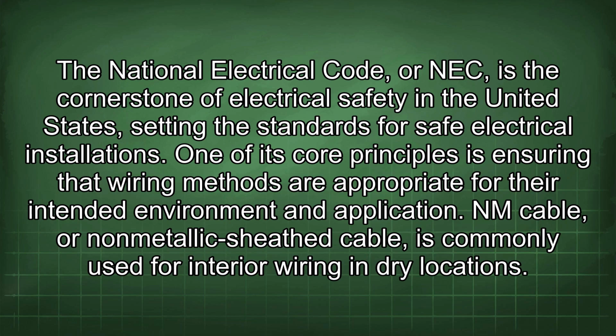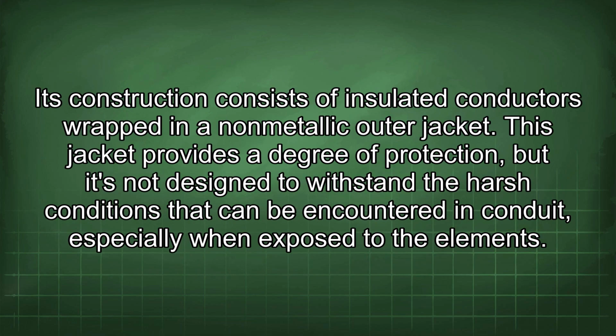One of its core principles is ensuring that wiring methods are appropriate for their intended environment and application. NM cable, or non-metallic sheathed cable, is commonly used for interior wiring in dry locations. Its construction consists of insulated conductors wrapped in a non-metallic outer jacket. This jacket provides a degree of protection, but it's not designed to withstand the harsh conditions that can be encountered in conduit, especially when exposed to the elements.